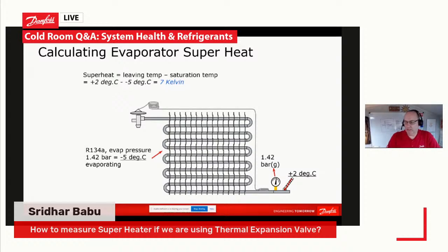It might be we are getting confused with the terms, or I'm getting confused with the terms, Sridhar. If we're using any form of expansion device, we know what we are evaporating at because we can measure our pressure. We convert that to our temperature using our refrigerant slider, and then we measure the outlet of the evaporator. So we can always measure our superheat that we have on our evaporator. So I hope that answers that question. If not, then please come back to us in the chat and we can take it a little bit more.